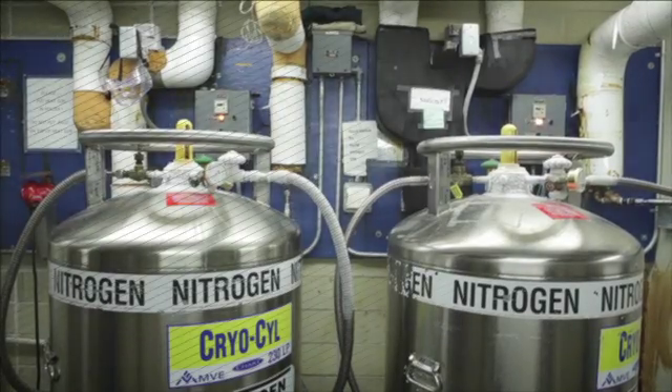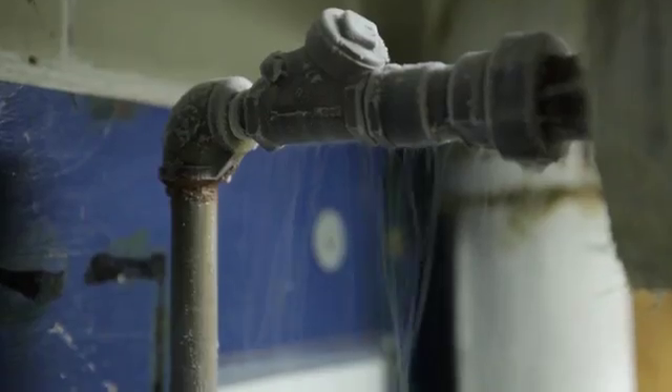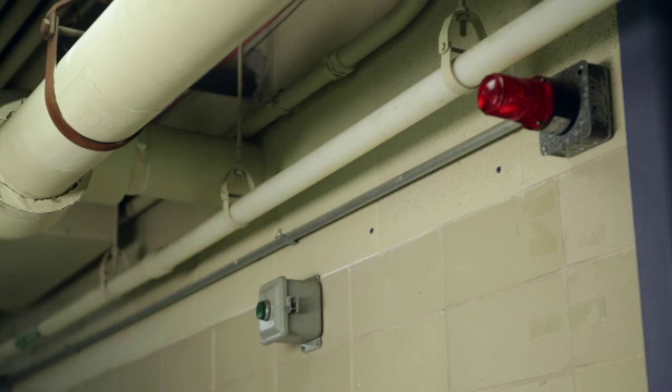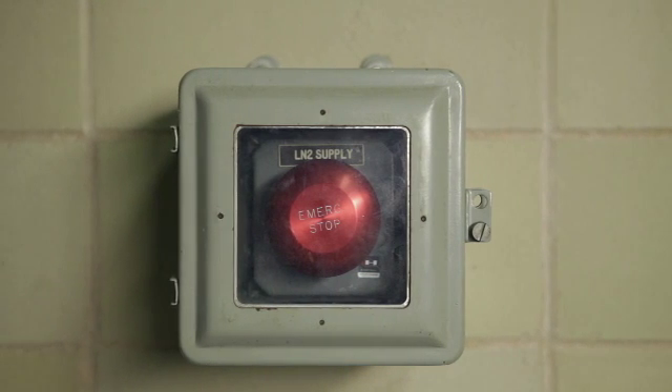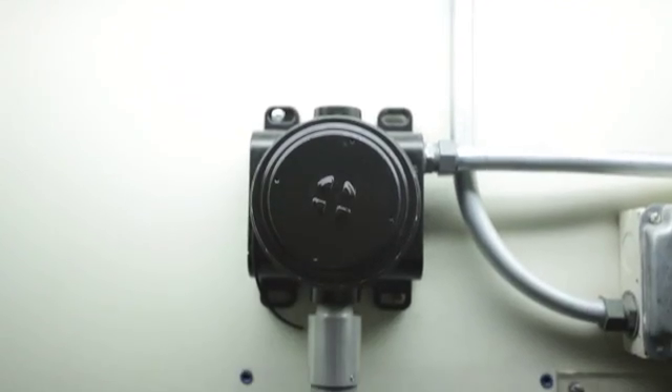Responding to emergencies inside the liquid nitrogen facility. If the liquid nitrogen supply system does not shut off or there is a break in the liquid nitrogen distribution system, take action: exit the room, locate the emergency shut-off button outside the facility and push the button, then call emergency services. A bulk liquid nitrogen facility must be equipped with an oxygen depletion alarm. If you hear this alarm or see the red flashing lights indicating an unsafe condition, exit immediately and call emergency services.